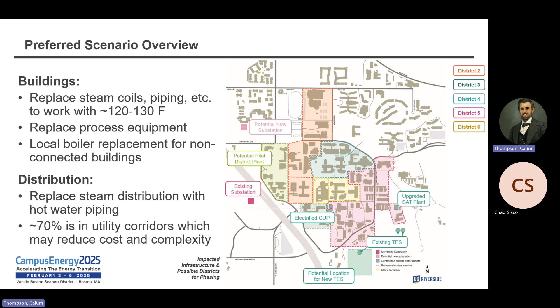The big shift, though, is how you pull out the existing steam pipe and implement new hot water piping while minimizing disruption, which requires a lot of temporary heat generation at buildings and a very clever phased approach. We identified 5 phases of transition, with an optional additional pilot in phase 1 to test out these technologies and see how they work in practice.